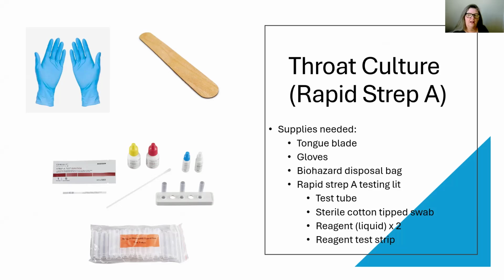Now, they all have expiration dates on them, so we always check the expiration date. But in addition to that, we want to make sure we got a good batch. And these are created in batches. So that's why we only have to take one test out and test it, because if one of them's good, theoretically, they're all good. If one of them's bad, theoretically, they're all bad, okay? Usually you have a log in an office to keep track of doing these controls, or many offices will just take a Sharpie and write on the box QC'd, quality controlled, and then put the date and the initials of the person who did it. That way everybody knows that that open box has already been checked.